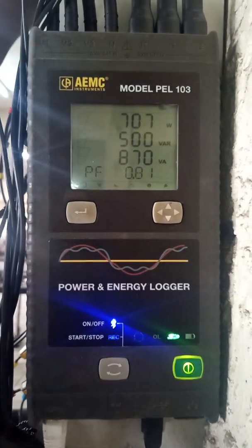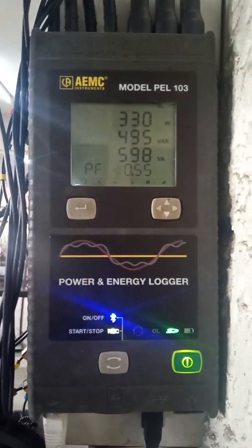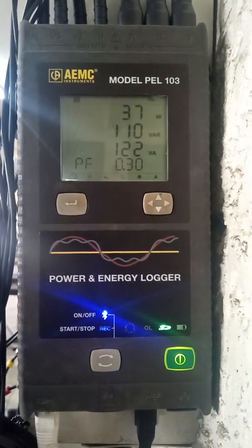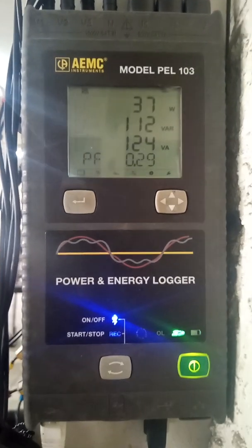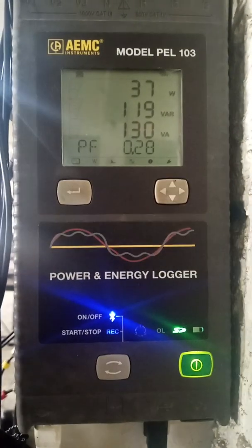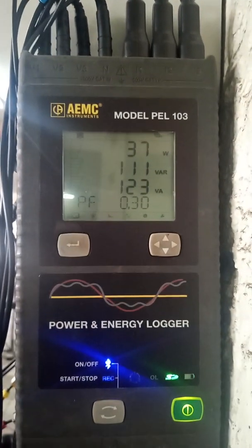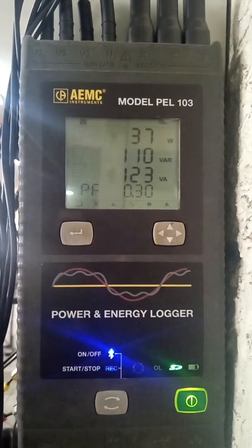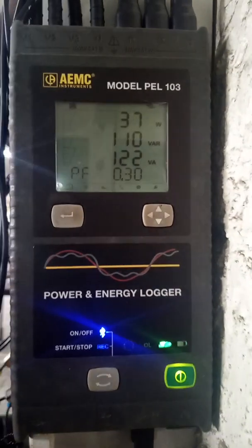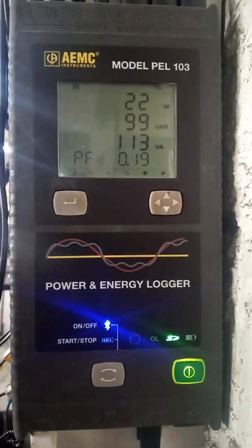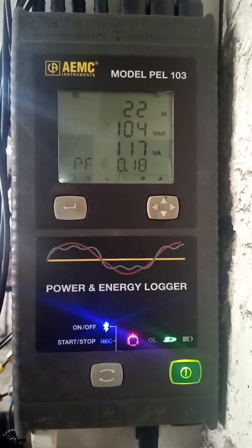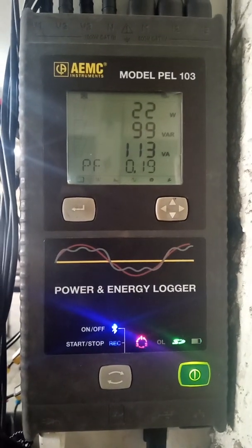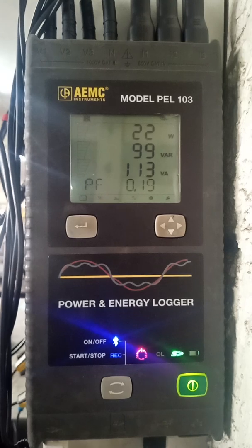Now I want us to focus at the machine again. I am going to switch off again — we want to remove the base load so that we are consuming zero. I have switched off one machine that was basically heating glue. Notice we are going to 37. That is what should be. When you are not using a machine, please ensure it has been switched off. Now this is the other base load for the other machine — I will switch it off. Notice these are part of the losses. We expect it to go even lower because there is nothing being consumed on that line except a bulb that is running on the same line.